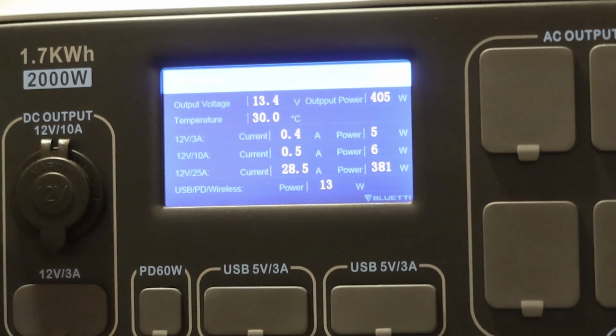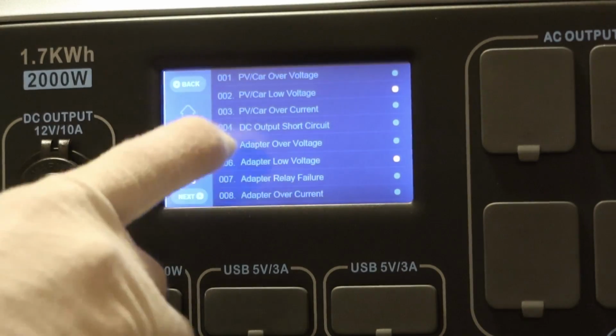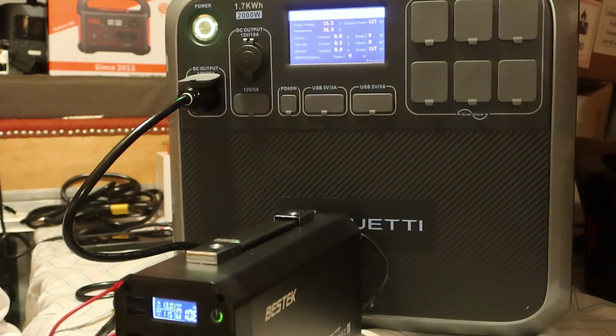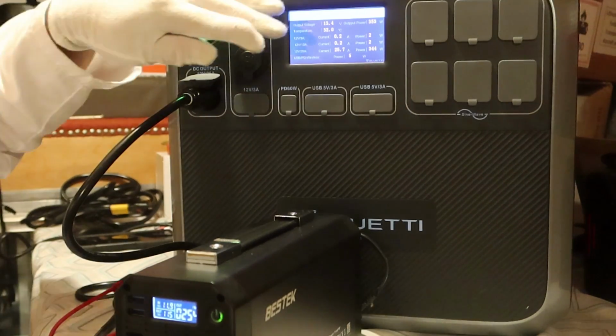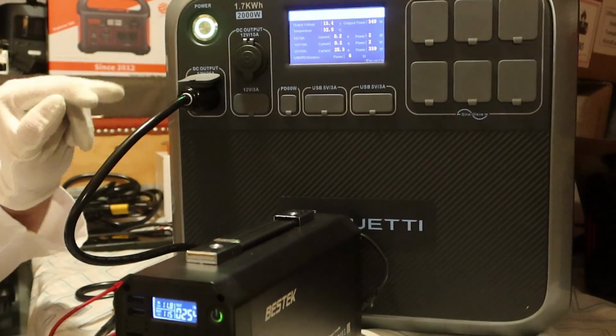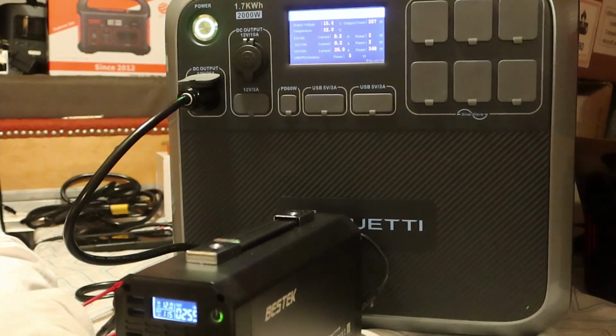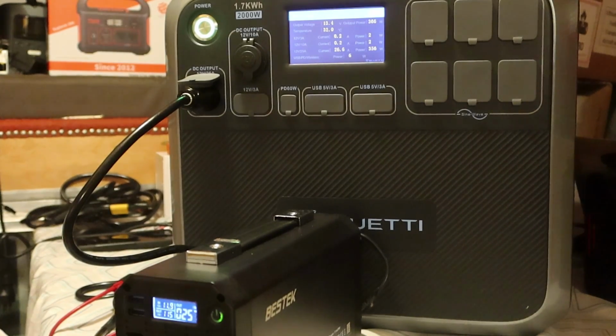Okay, we're at 28 amps, and we got the shutdown. We clear the fault, take it back up to 25 amps again, 350 watts. Down here it says 254. So that shows you there's actually a 100 watt loss between converting from DC to AC. 27 amps, 27 and a half, 27.8, 28.